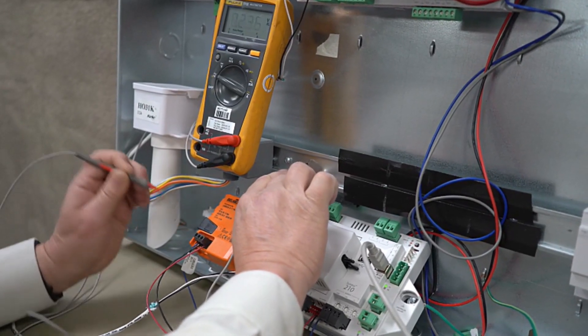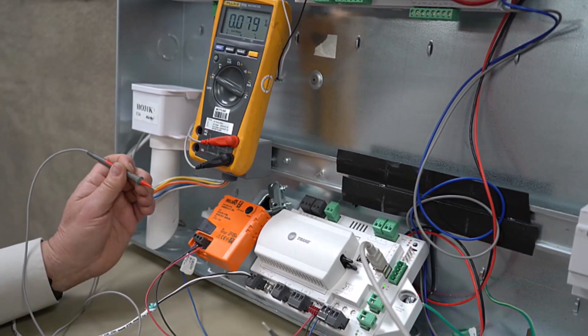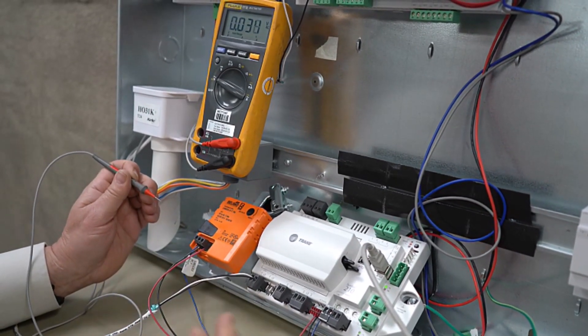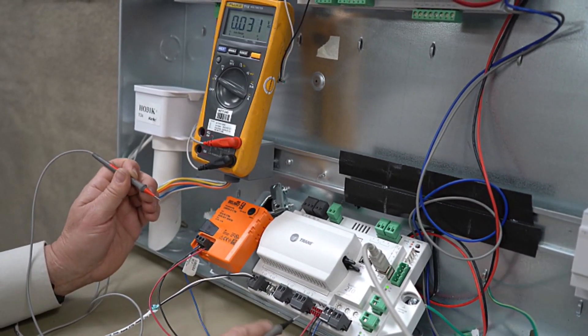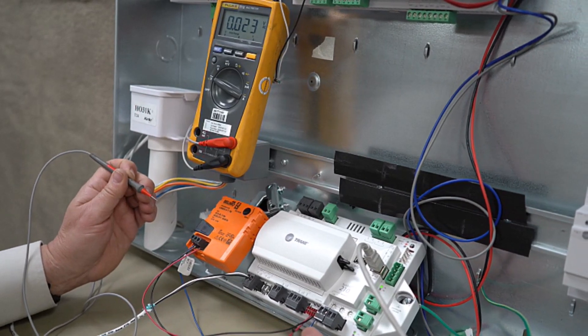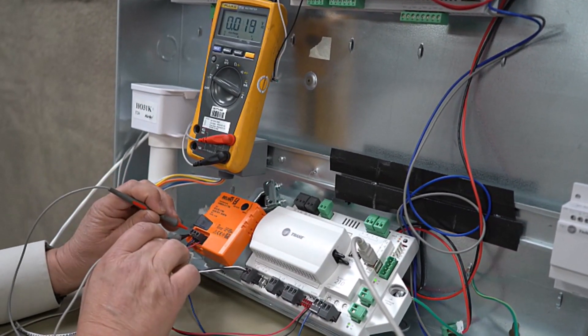So that black and that red wire is what we use to drive open, drive closed. When we tell this actuator to drive open, then basically it will short that leg to ground, completing the circuit. And so as we measure across here, we will get that voltage drop coming across.